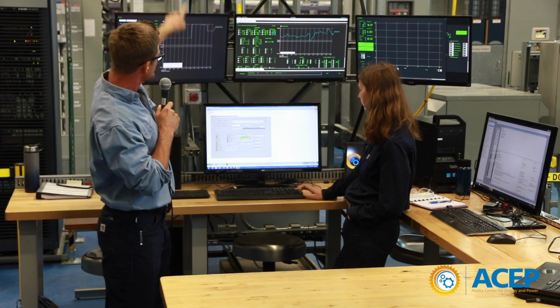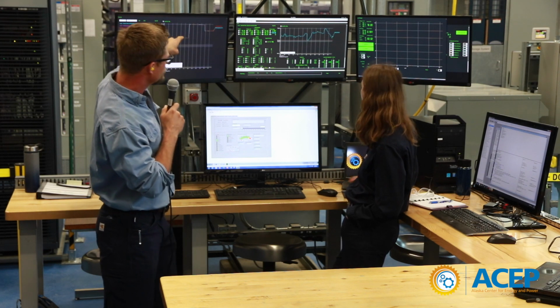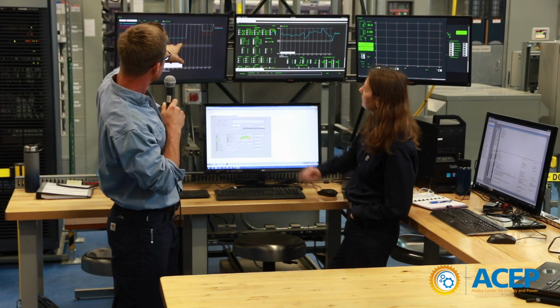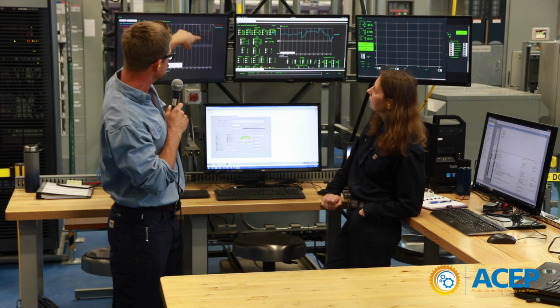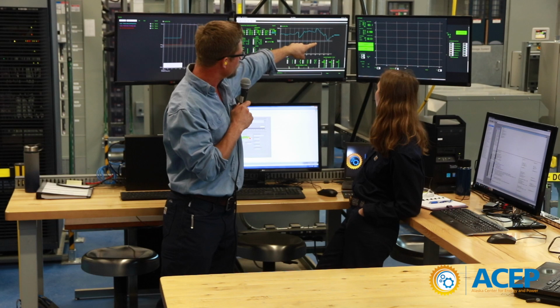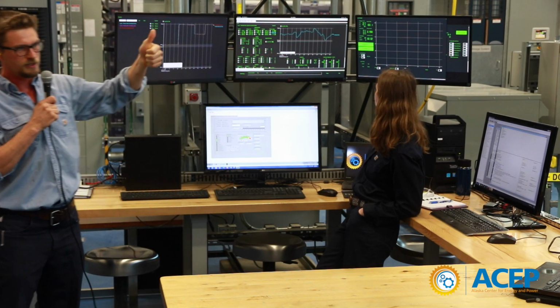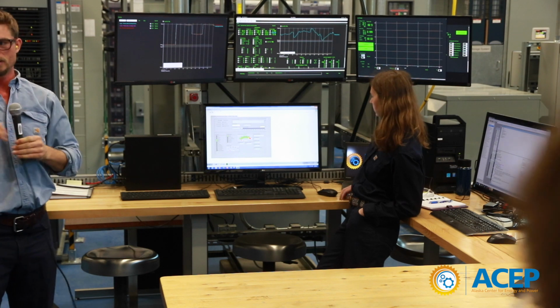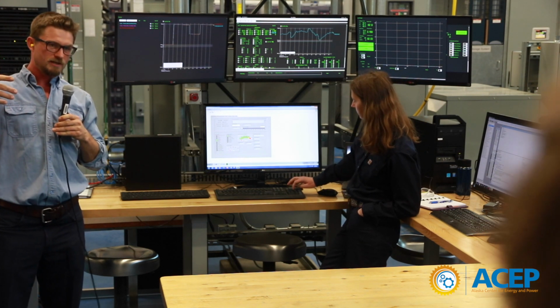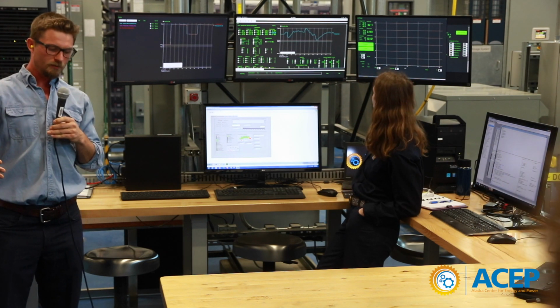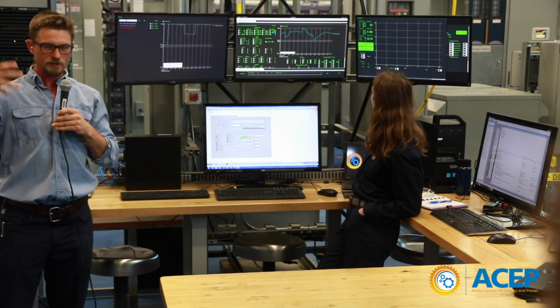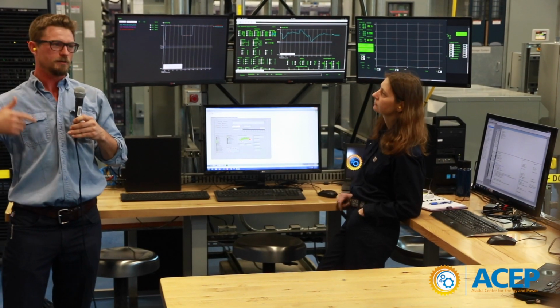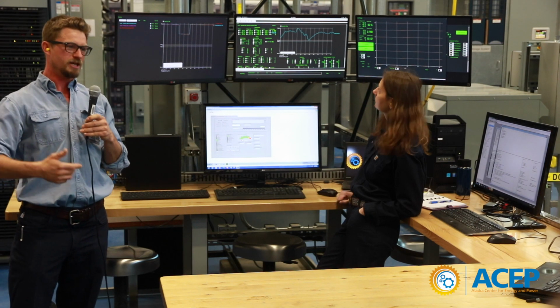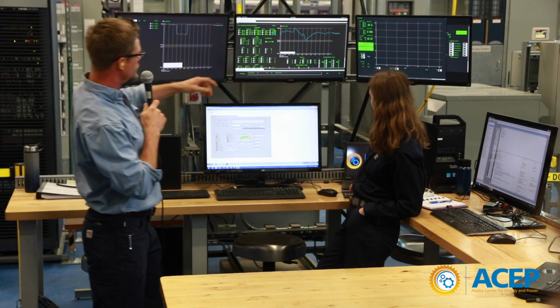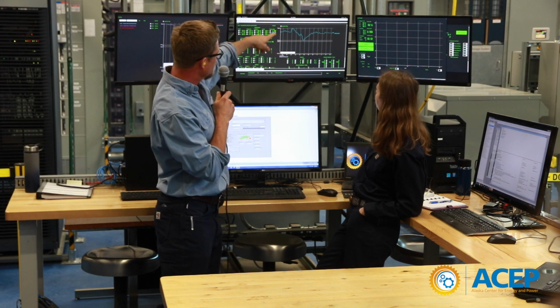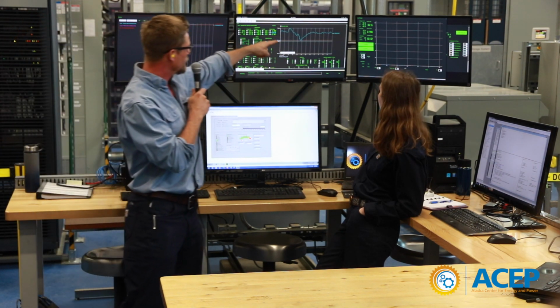You can see Tana just bumped up our load from 50 to 100, and our load just bumped up, down, and up again. You can see our grid frequency responds: when you have a step increase in the load, your frequency goes down, because your generator is a spinning machine, and when you put a load on and increase the resistance to that spinning, it slows the machine down until it's able to respond by putting more fuel into the engine and increasing its power to speed it up again. That's why you see this drop in frequency, and when you do the reverse and remove load from the system, you get a little bump in the frequency.